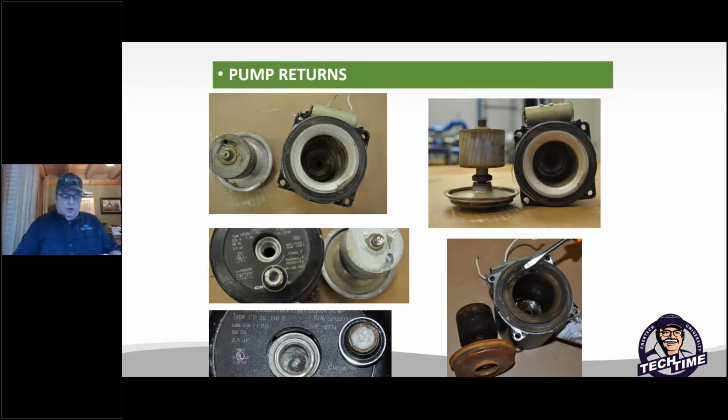Okay, so I wanted to show you a pump that I have. As you can see, discoloration, kind of a reddish color, and I think that's a lot to do with the high iron content. And when you start looking at the pump itself, the little bearing surfaces, everything is rusty red colored. Well, there's a reason why this pump didn't last.